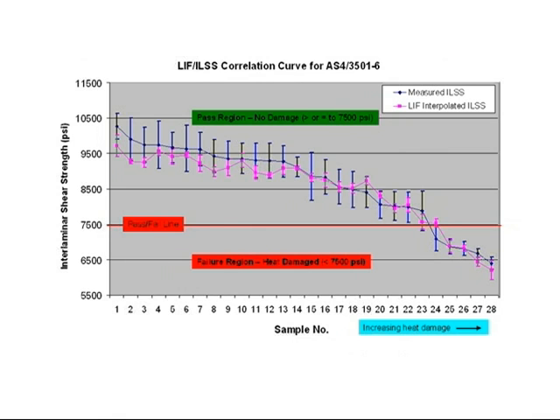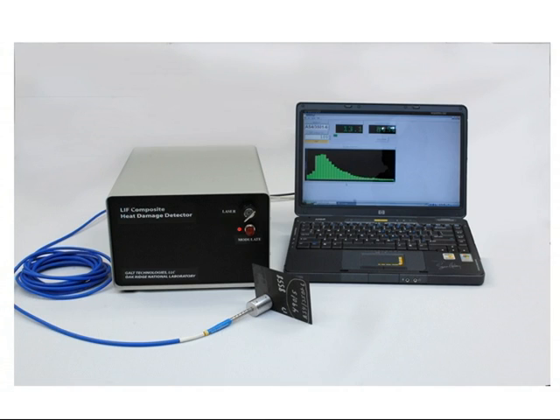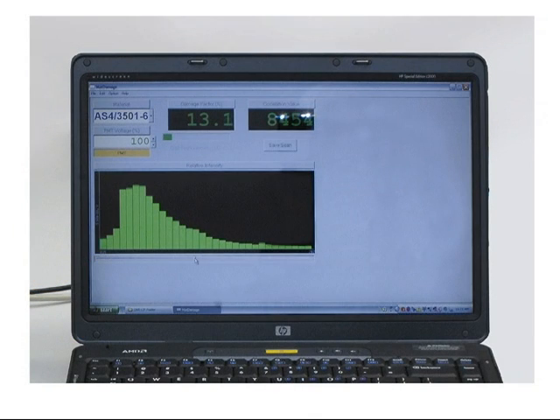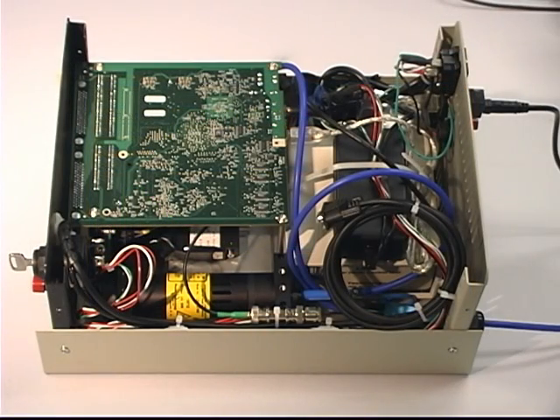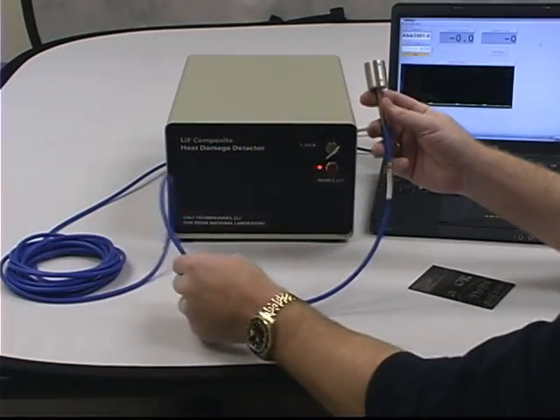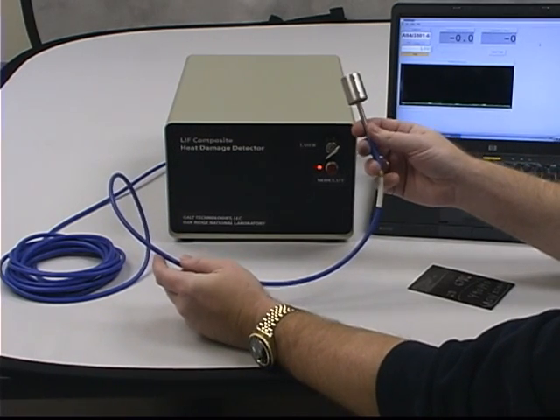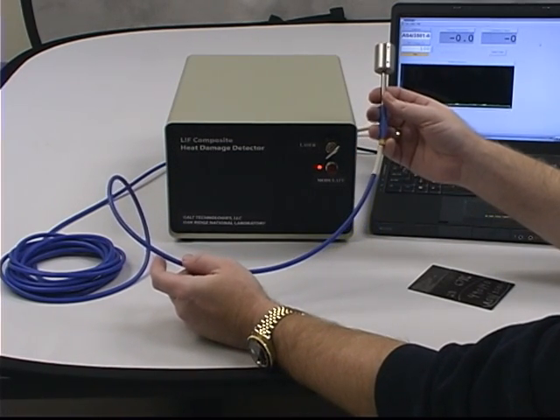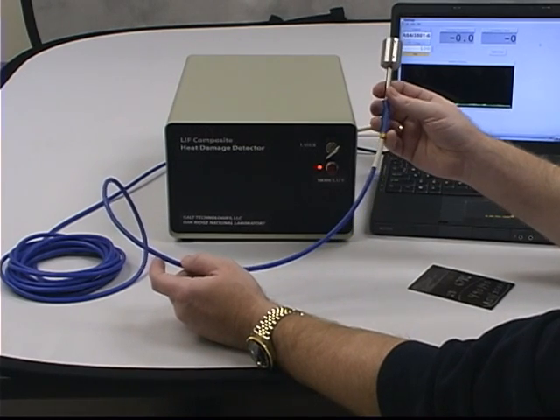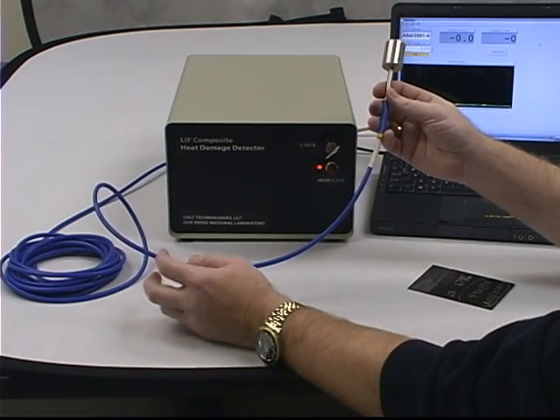There are two major components of the laser-induced fluorescence composite heat damage detector: the LIF unit and a laptop computer. The laptop runs custom software that provides a graphical user interface to the LIF unit. The LIF unit contains the excitation laser, the spectrometer, photomultiplier tube, detector electronics, analog to digital converter, and power supplies. A flexible reflection probe is used to deliver the diode laser excitation and recover the induced fluorescence. Use of a flexible probe allows the user to detect and monitor heat damage in remote or limited areas.